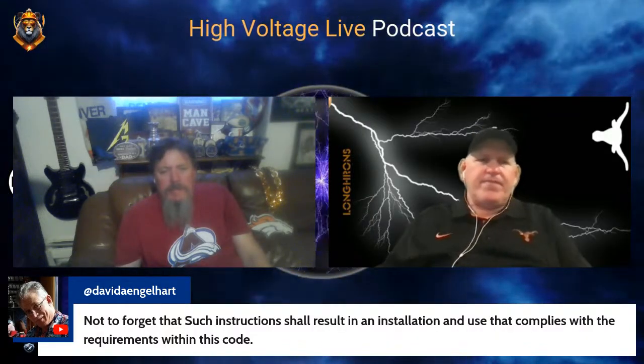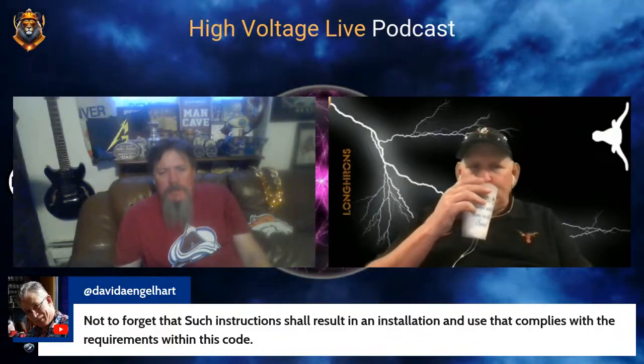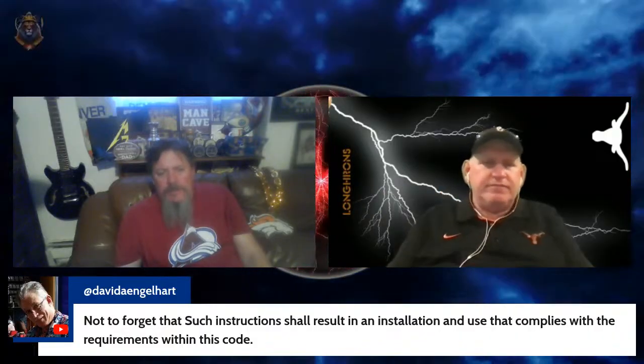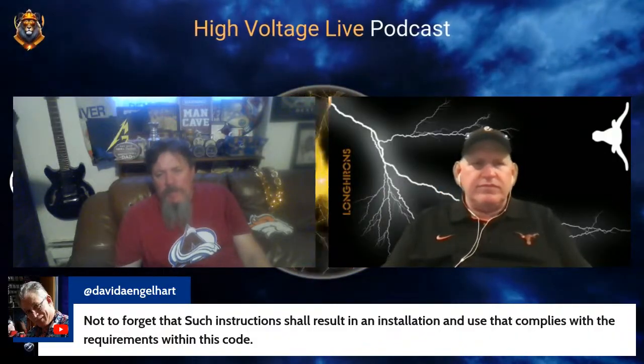Yeah, and that is an interesting thing, David, because those manufacturer instructions say do not put it on GFCI, but that is not a refrigerator receptacle. That's a kitchen receptacle, and it says all kitchen receptacles require GFCI. So that manufacturer may not remove that requirement for GFCI.